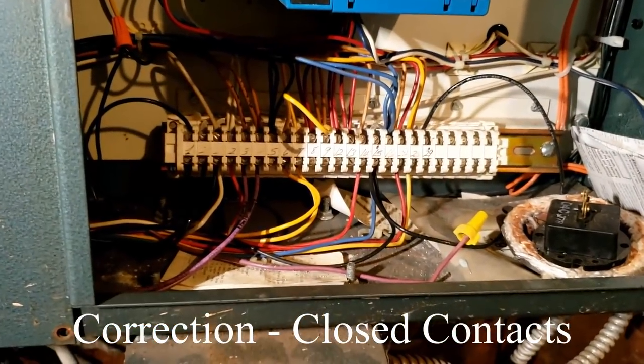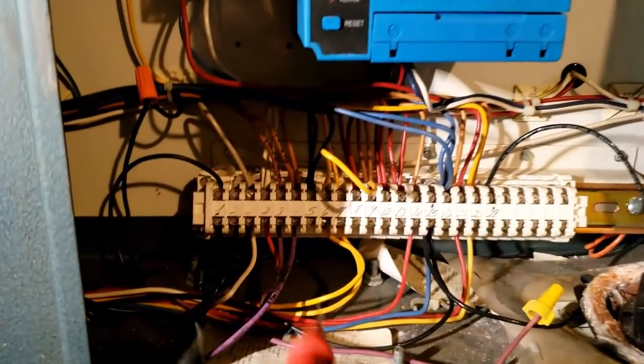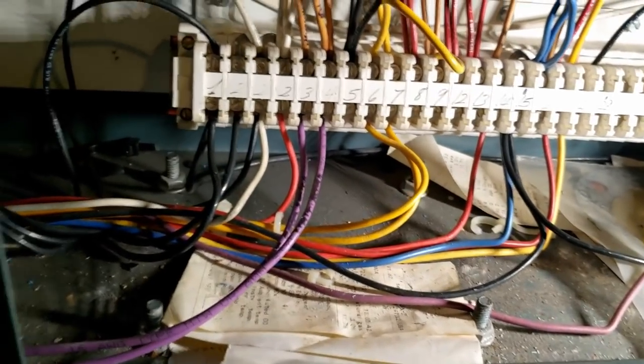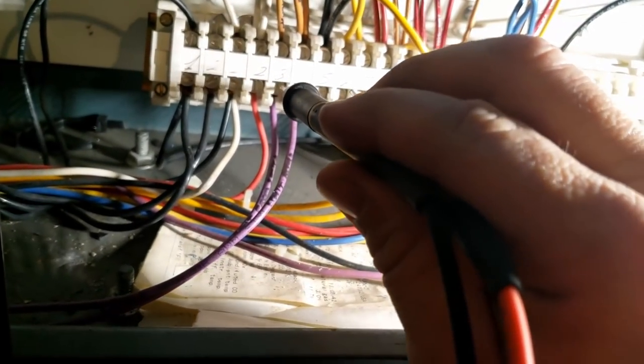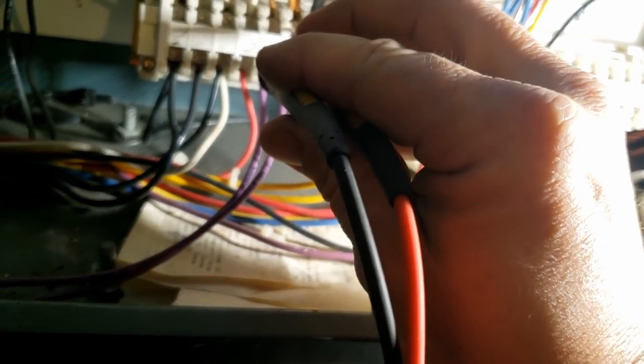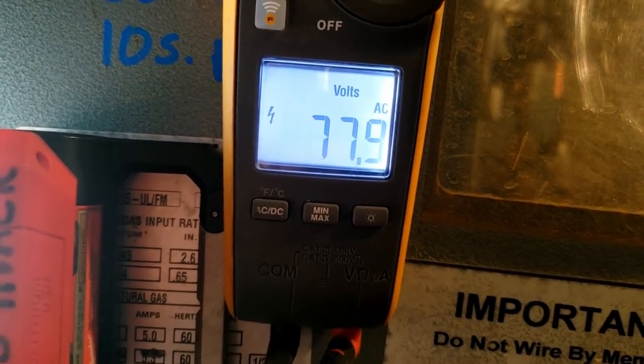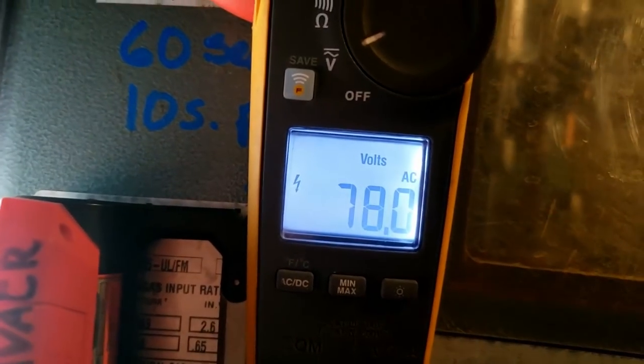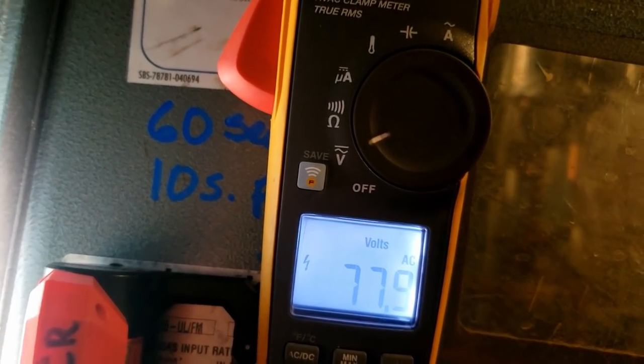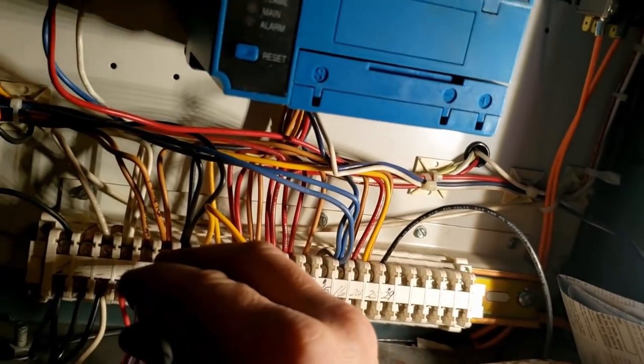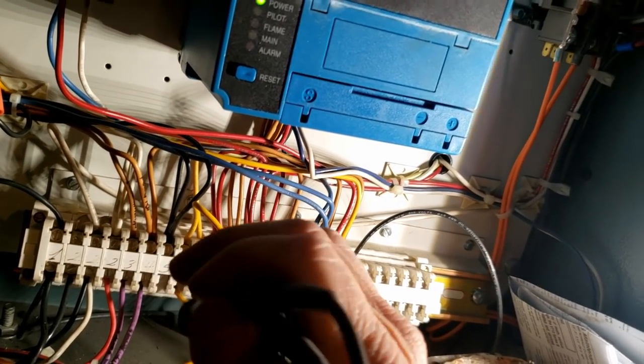One and two, it's my thermostat. Let me check those real quick. Alright, so the two purple wires, three and four, have a weird voltage on them. They are right in there at 77, 78 volts. So it's not completely open, it's not completely closed. So we've got an issue there, but we're not sure which one it is because these are all in basically a series loop, one to the next to the next to the next.